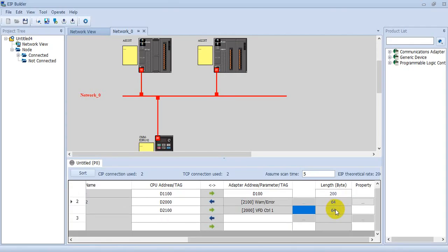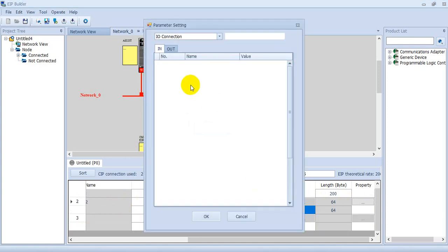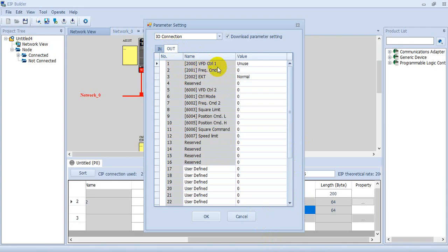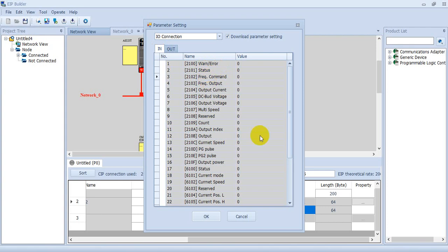And then let's go to the MS300 part. So what we want to show is give a frequency command from PLC, then you will write to here, and we can monitor whether the value really comes or not. So we can see what we need to monitor is the frequency command, and the frequency command from PLC, and this one is the actual command received.